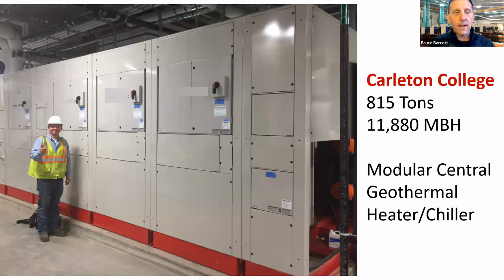This is our 850-ton geothermal chiller that we've got on campus. We're doing about 50% of their total cooling capacity. They still have another centrifugal plant, so it's a hybrid plant. We're simply tying into that master loop and providing, we're the first on chiller because we're the most efficient, better than the current centrifugal. So we're first on, runs as many hours as we possibly can, providing right now about 50% of the campus heating as well.